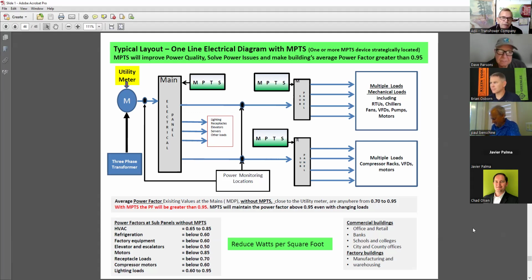All right, this is the last slide, and with that, I will stop recording. You can see multiple MPTS units are installed in a single circuit, and you can create this kind of scenario in any electrical network. Because MPTS acts like a ground rod sitting on top of the ground, it is better to have more than one MPTS if your network load permits, because you want more than one point to remove harmonics, because harmonics are the greatest threat today for power quality in electrical.